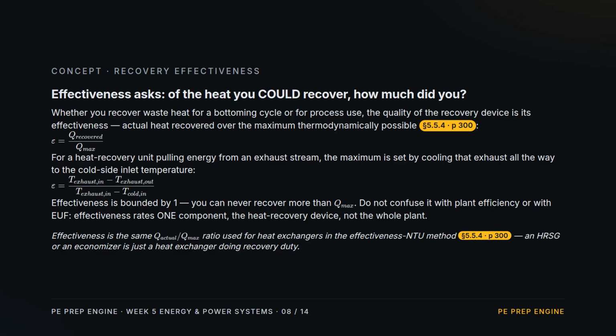For a unit pulling heat from an exhaust stream, the maximum means cooling that exhaust all the way down to the cold side inlet temperature. So effectiveness is the actual temperature drop over that ideal drop. It can never exceed 1. Do not confuse effectiveness with plant efficiency or with the utilization factor. Effectiveness rates one component, the recovery device, not the whole plant.